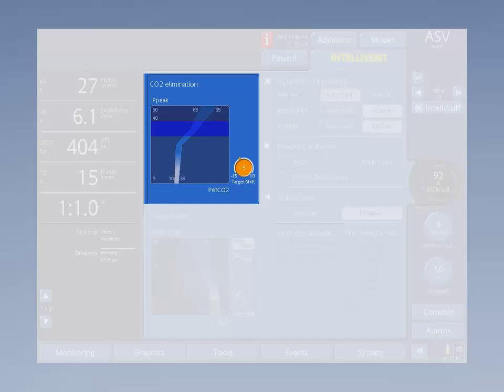If they want to increase CO2 removal and thus have lower ETCO2 levels, they can set the controller offset to the minus — the target ETCO2 area will then shift to the left. If ETCO2 is too low, the offset will be put to the right. The ability to change the offset allows physicians to take circulatory and metabolic state into consideration and adjust the automated therapy goals.